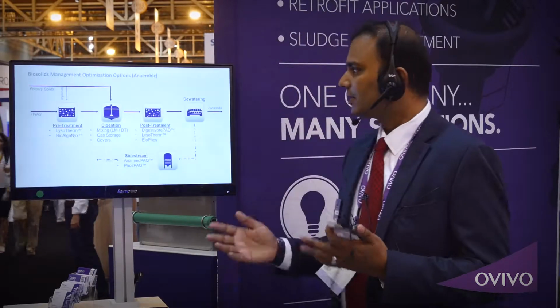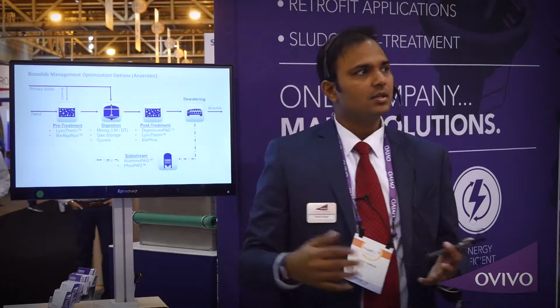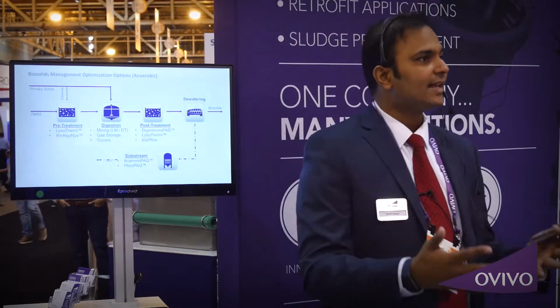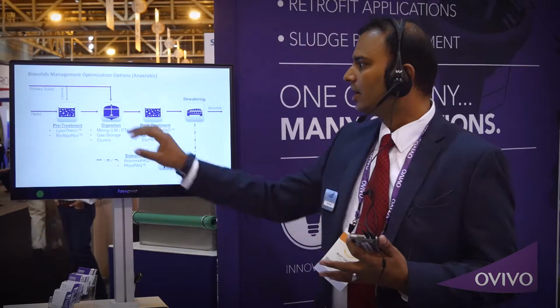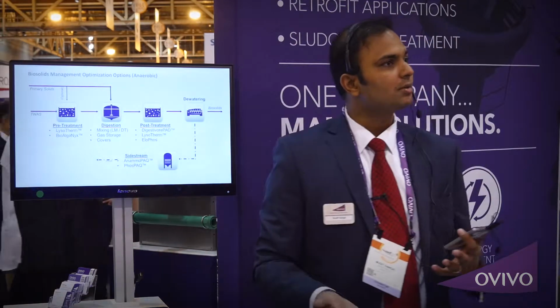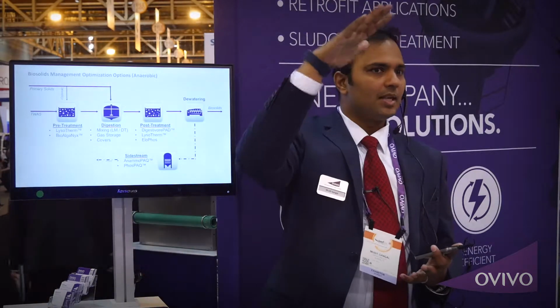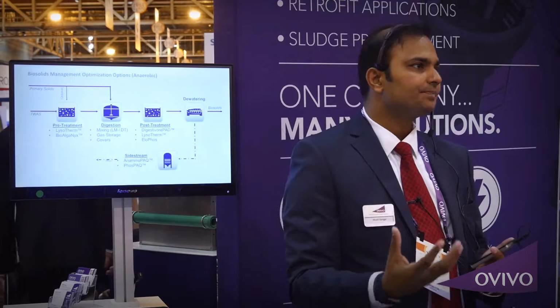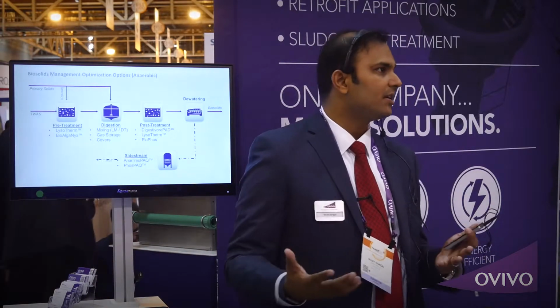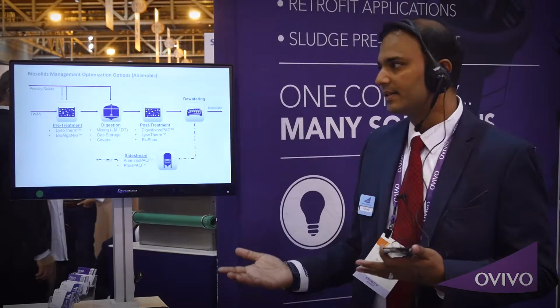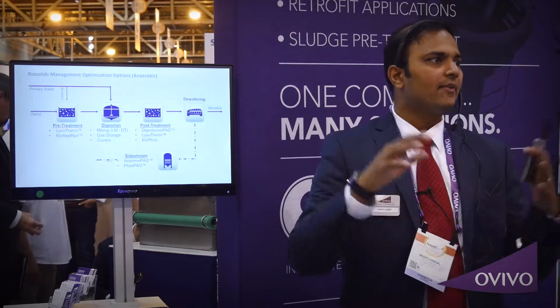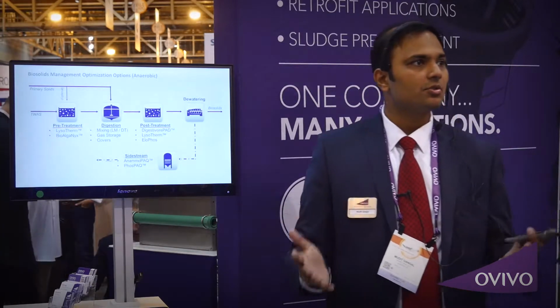So under such circumstances, how can you manage anaerobic digestion? What are some of your options to optimize it, to enhance it, to address those challenges and the opportunities that we're discussing? Looking at the digestion itself, on the mixing side, there are several types of mixers available. One of them is right here in front of you, which is the linear motion mixer that the OVIVO offers. The principle is basically reciprocating action by the mixer, which causes the mixing in the digester. And the key thing is it uses a very low amount of energy. You're talking a tenth or even lower amount of energy for mixing a huge digester as opposed to standard mixing systems. In terms of gas storage, you could have steel covers or membrane gas holders to do that.